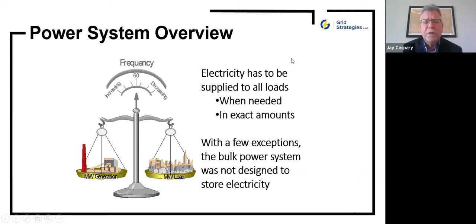If a huge amount of new load pops onto the system—maybe some arc furnaces starting up—or a big generator trips, there's an imbalance and the frequency will decline. Fortunately, there's a lot of mass, inertia, and governors out there that respond from the traditional thermal units, converting kinetic energy into spinning mass to bring the grid back to 60 hertz. If there are significant imbalances, at some point we'll actually curtail load—there are under-frequency load shedding programs, and those get implemented more often than I'd prefer.